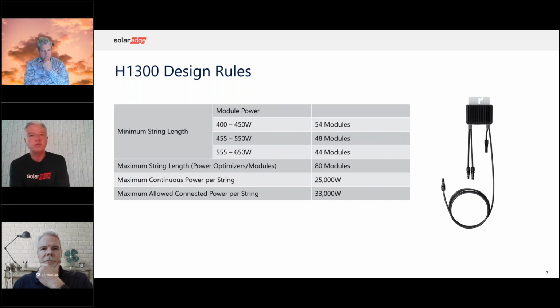Some of the design rules with the H1300. So you can have strings up to 80 modules in a string. Now that's significantly more than any other 1500 volt inverter on the market. Depending on the power class, you can go up to 80 modules in a string. And then minimum is 44.